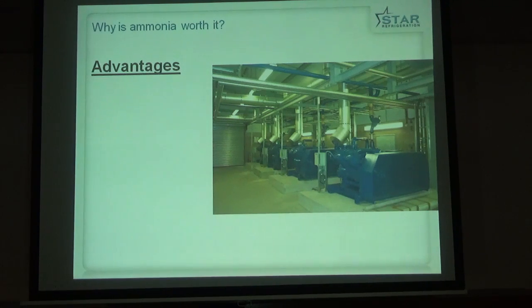Lots of advantages to using ammonia as a refrigerant. It's efficient, it's cheap, it's reliable, it's very widely available, it's easy to get hold of the ammonia for the refrigeration system. It costs about a pound a kilo, something like that. If you go and buy an HFC refrigerant, you're probably paying five times that if it's just a straightforward R134A, 25 times that if it's a more complicated blend chemical. And ammonia refrigeration is actually very easy, it's very reliable. It's easy from a maintenance point of view. So lots of things going for it.